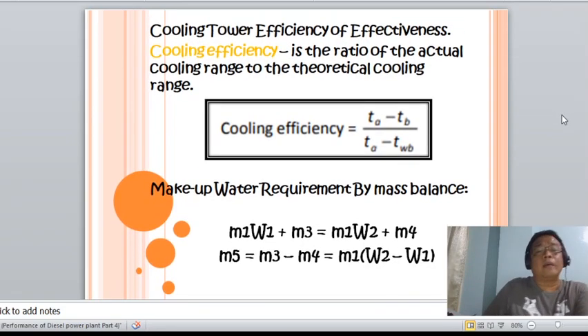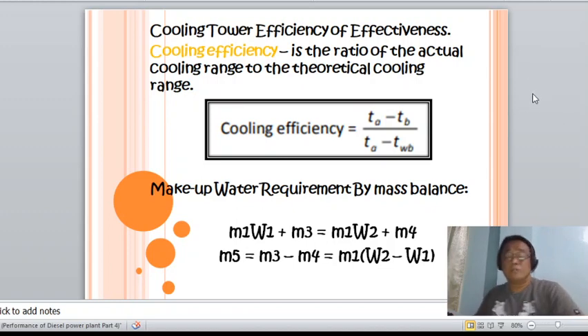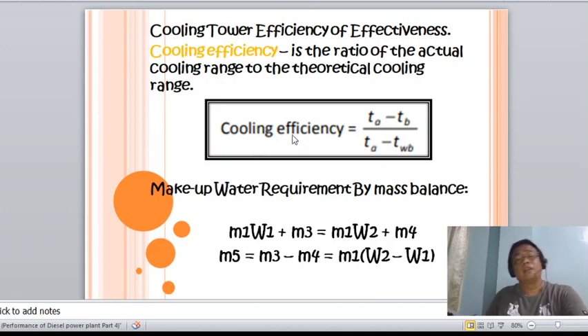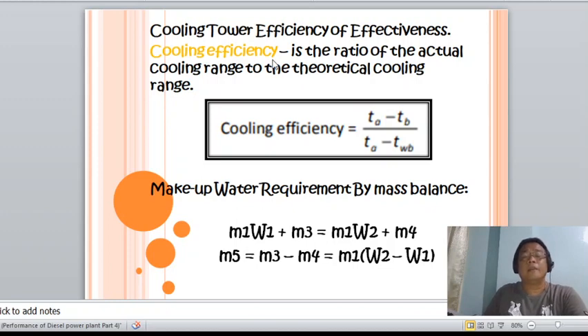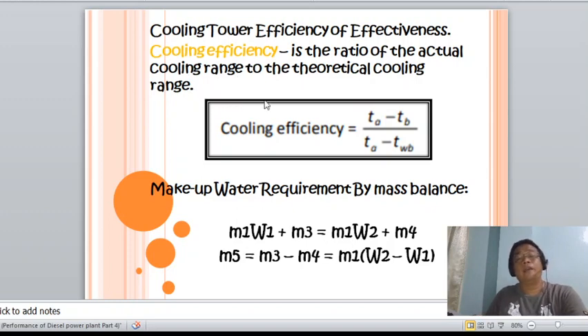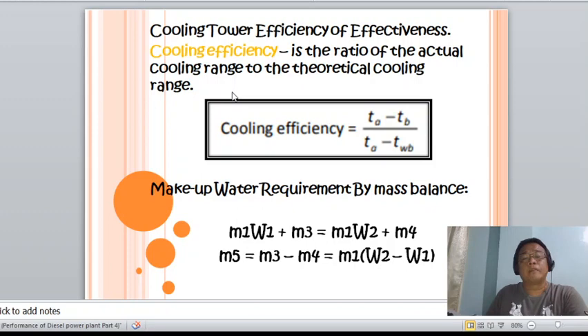We also have the cooling tower efficiency, or effectiveness. This measures the effectiveness of the mechanical equipment of the tower and is the ratio of the actual cooling range to the theoretical cooling range. The theoretical cooling range is the difference between the temperature of the entering hot water and the wet bulb temperature of the entering air.